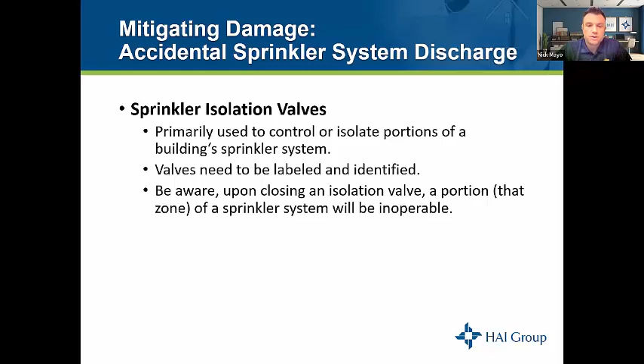Usually on a sprinkler system, the main control valve will be chained and locked in the open position, and the only person who can either open that lock or shut the sprinkler system down from the main control valve is going to be a fire department rep or a third-party contractor working on the system. But the small isolation valves within the branches of the system are just the branches that they would close if they have to replace a sprinkler head that was broken or activated.